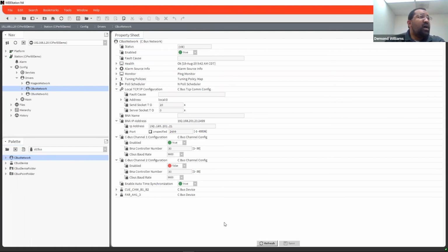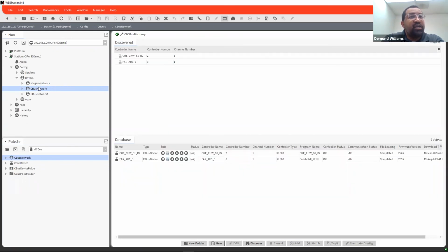So that is the good thing, and that's pretty much the way that I'm marketing this system. Like I say, once you get your controllers and everything in here, just remember the controllers themselves are actually one device, but you need to take into account how many air handling units or fan coil units or VAV boxes are underneath each one of those devices, and you want to make sure that you add controllers accordingly to your CIPer 50 or to your JACE 8000 or to the supervisor themselves.